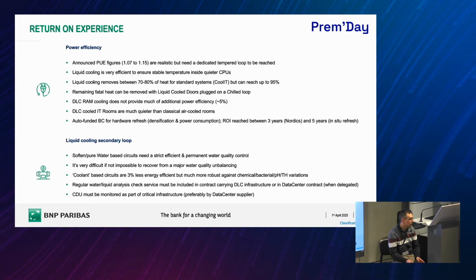It's almost impossible to recover from a major water quality imbalance. Once it happens, it's too late - it's like a swimming pool. If the swimming pool turns green, it's over, you have to empty it and refill it completely. In a DLC system, that's not even possible. So if you go to pure water-based systems, you have to be perfectly aware that maintenance is key to the success of the system, and it should be absolutely rigorous.